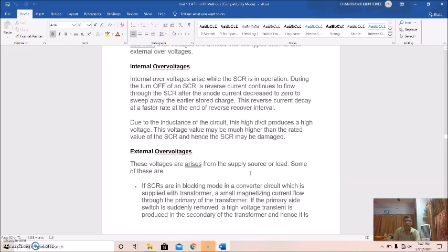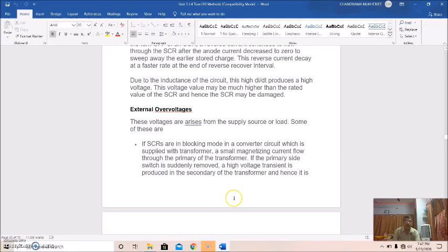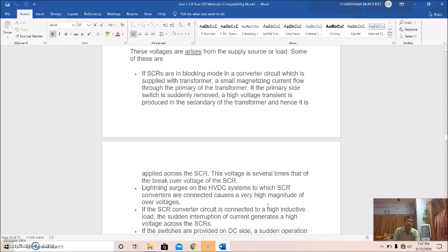Now, external overvoltage arises due to supply sources or load. Some of these: if the SCR is in blocking mode in a converter circuit which is supplied with a transformer, a small magnetizing current flows in the primary of the transformer. If the primary side switch is suddenly opened, a high voltage transient is produced in the secondary of the transformer, and it is applied across the SCR. This voltage is several times the breakover voltage of the SCR.